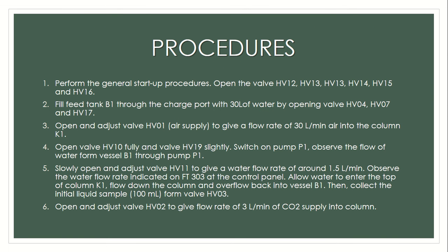So after we perform the general startup procedures, we can run the experiment. So these are the experiment procedures, I'm sorry. The first one is perform the general startup procedures and then open the valve HV12, HV13, HV14, HV15 and HV16. Then fill feed tank B1 through the charge port with 30 liter of water by opening valve HV04, HV07 and HV17.